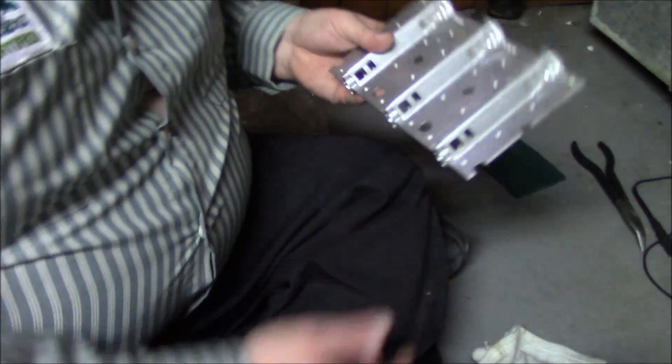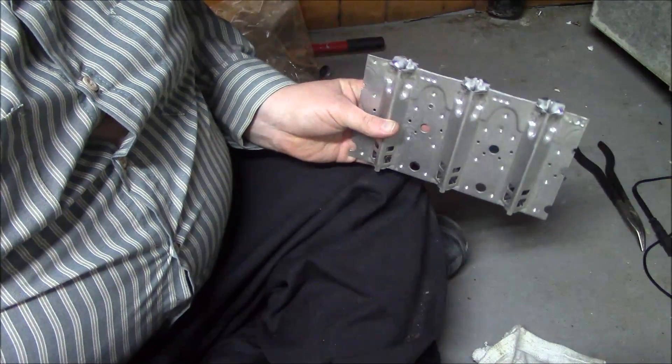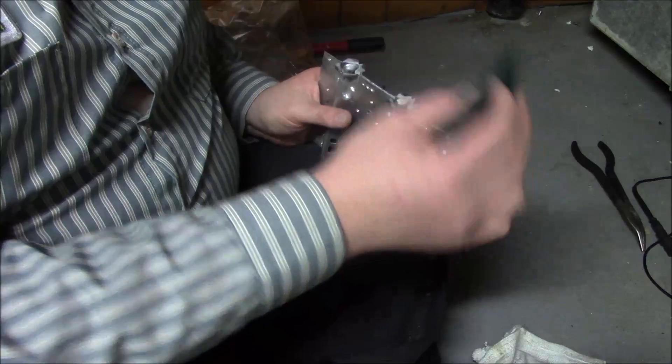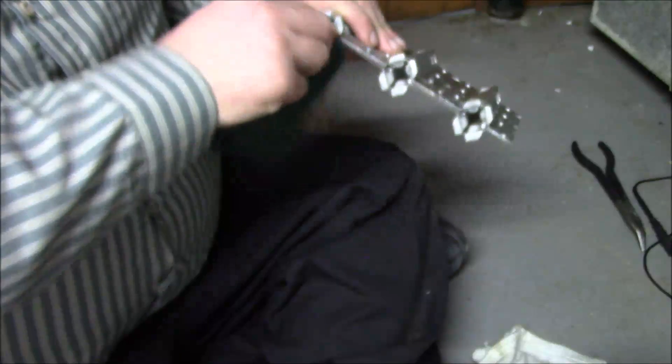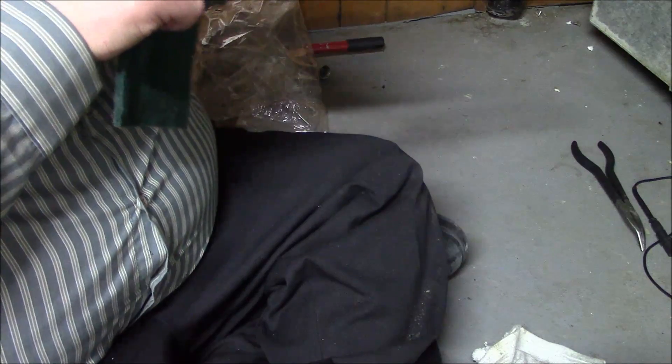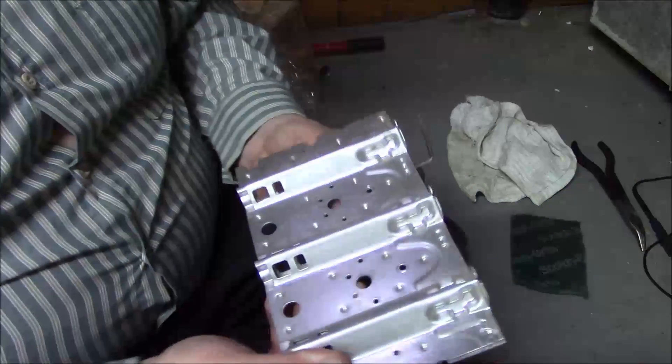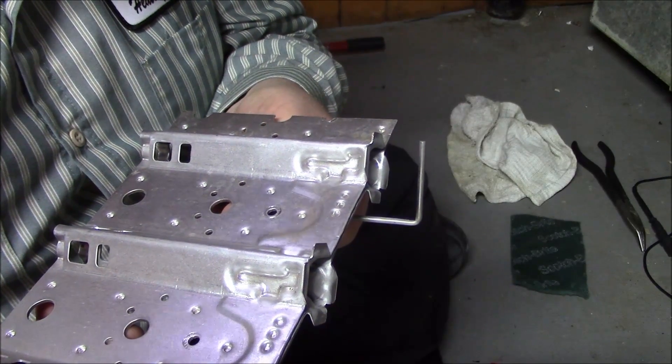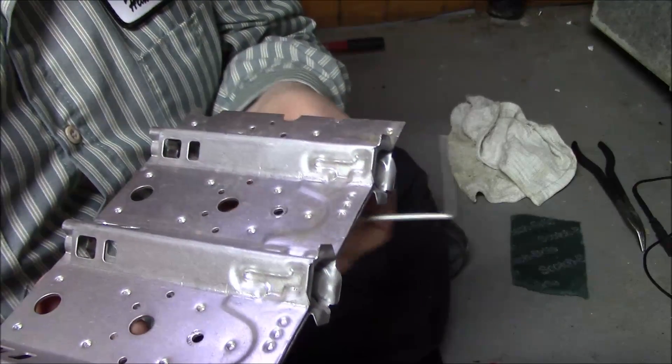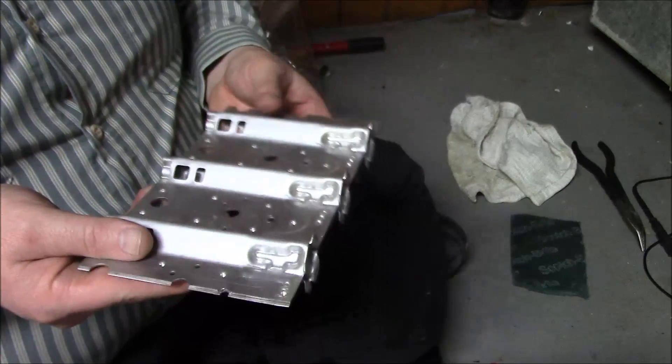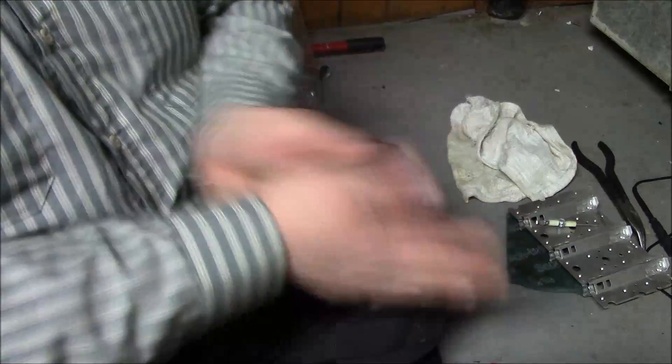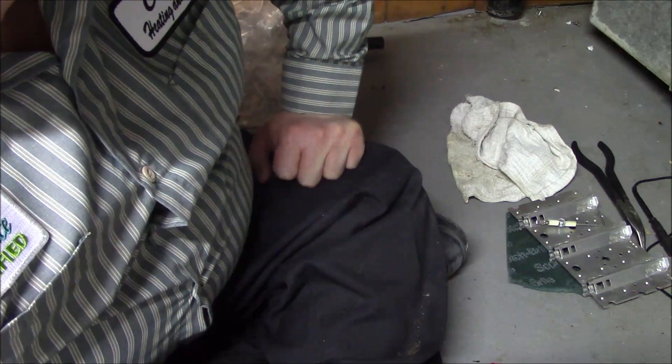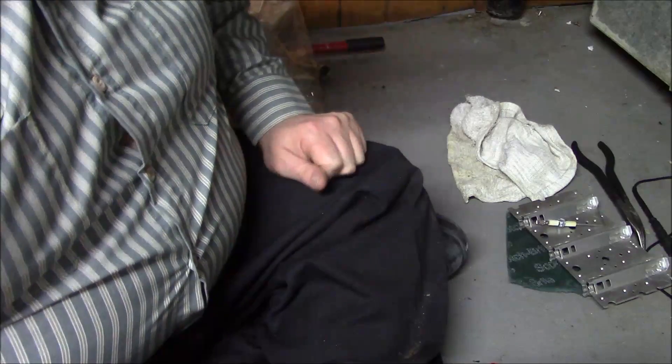Now when we look at this bad boy - igniter, flame sensor - take the scotch-brite and just knock some of that heavy soot and everything down, because you want to make sure you get good contact from this sitting here. That inner blue cone on that flame conducts electricity. You want to get the signal that goes from the board to here through the flame to your ground. You don't get that, incomplete circuit, it won't work. There we go, that's what we want.